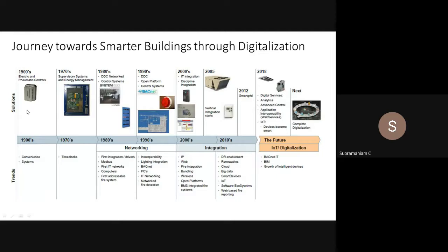Coming from there, in the 1970s the supervisory system and energy management system started coming. In the 1980s, DDCs and the Modbus protocol started coming. Then in the 1990s, in 1995, the most important breakthrough was ASHRAE BACnet. I remember in 1987 the first committee was formed with manufacturers from the various BMS companies and end users, that is owners from universities and many others. They took almost 7 years to come up with the ASHRAE BACnet standard. In 1995, that BACnet standard came.